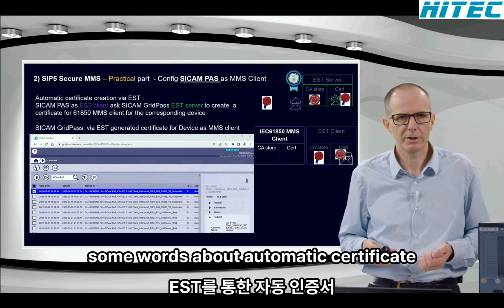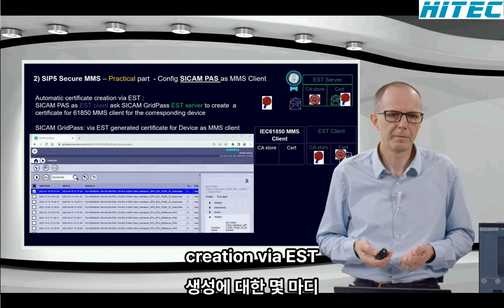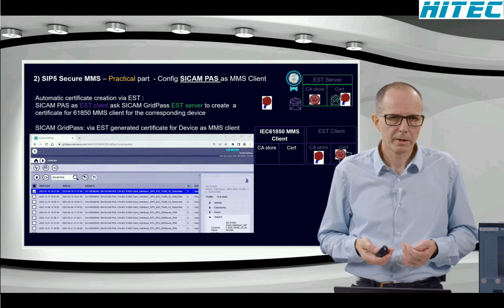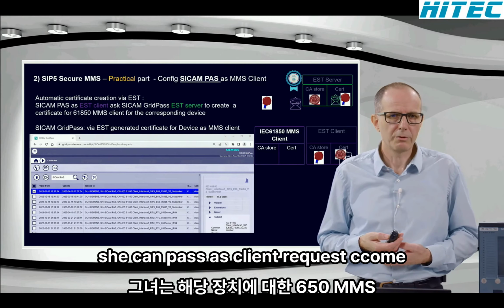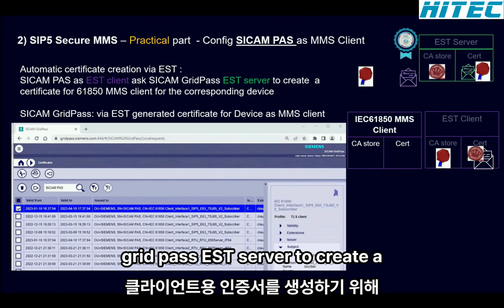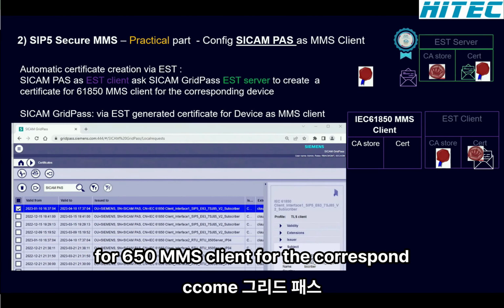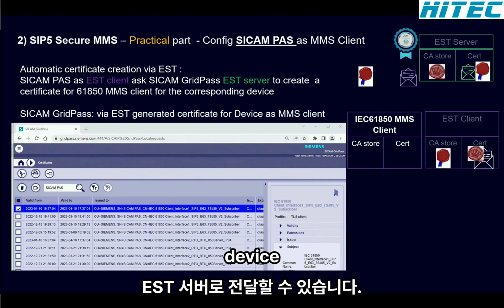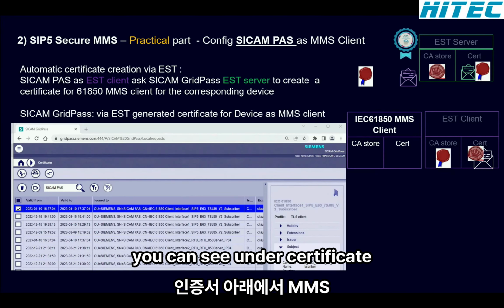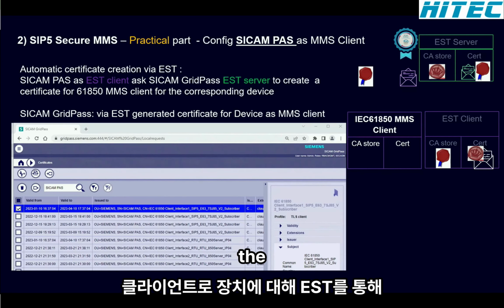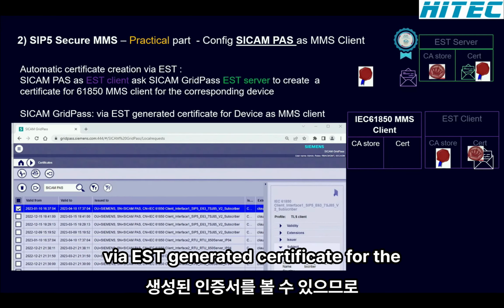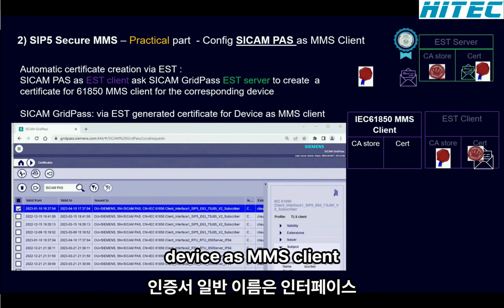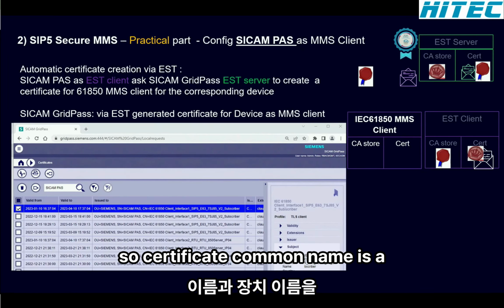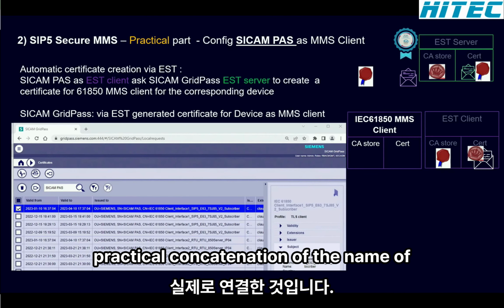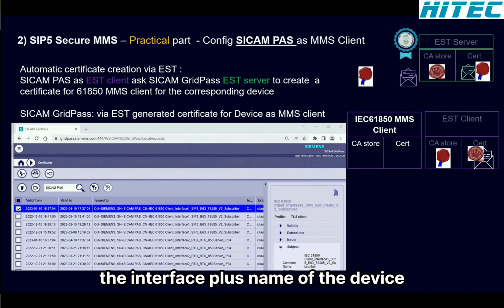Some words about automatic certificate creation via EST. SICAM PAS as client requests the SICAM GridPass EST server to create a certificate for the 61850 MMS client for the corresponding device. In SICAM GridPass, you can see under certificate the EST-generated certificate for the device as MMS client. The certificate common name is a practical concatenation of the name of the interface plus the name of the device.